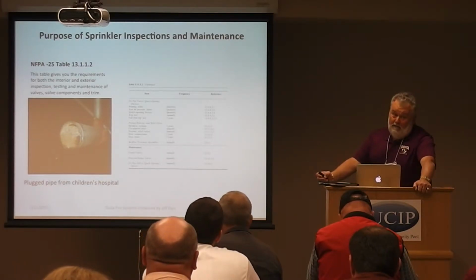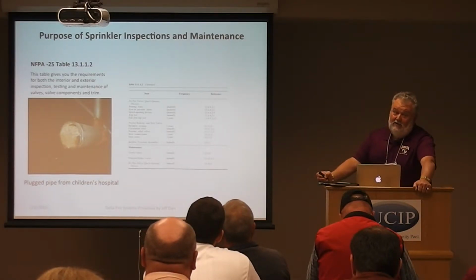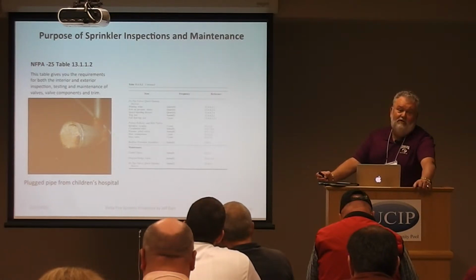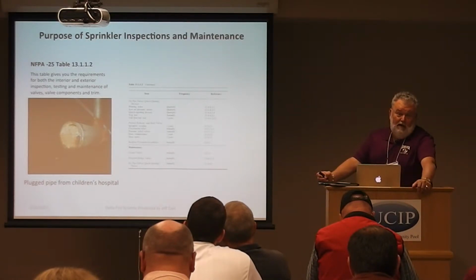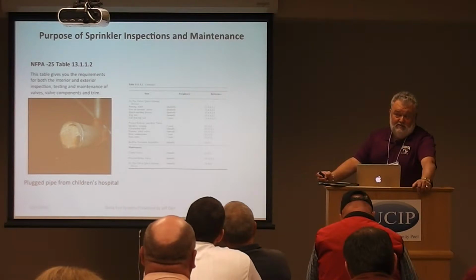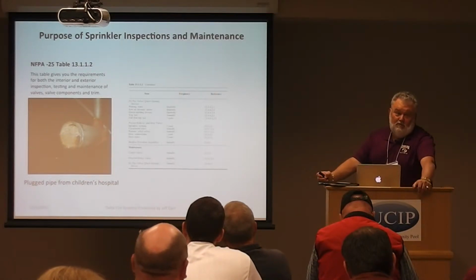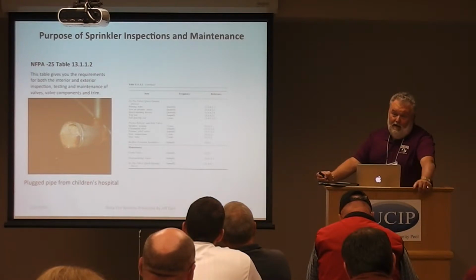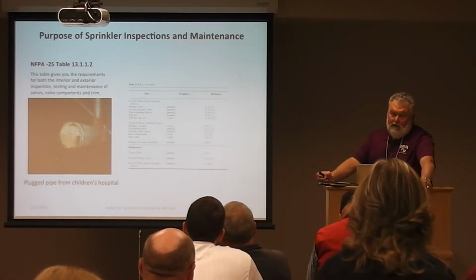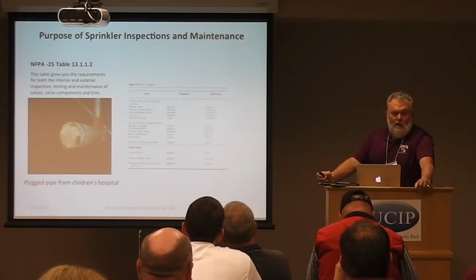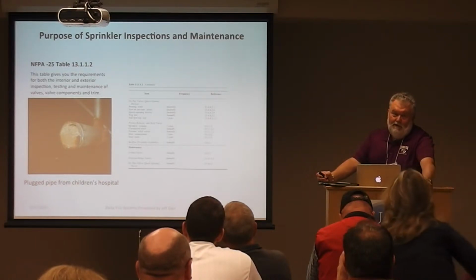Right, and there are requirements that every 5 years, we actually have to pull the end cap off a main and the sprinkler head off the line and investigate to see if there is any debris. If there is, we have to do further investigation, possibly flushing the entire system. And, I mean, we've actually had to remove entire systems before because certain areas with certain water got really bad over the years. And it's funny, I've been doing this now for 38 years. When I started, it was all Schedule 40 pipe, thicker wall, heavy pipe. Nowadays, it's Schedule 10 piping, lighter piping.